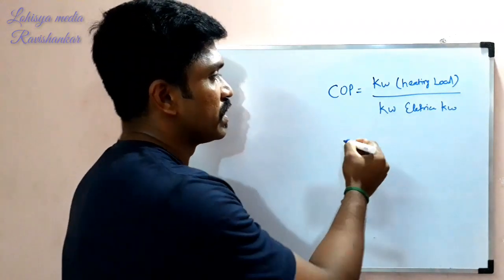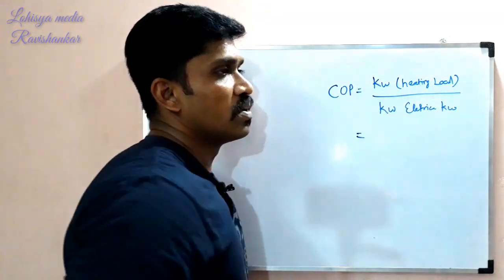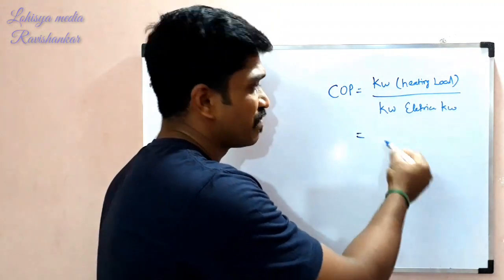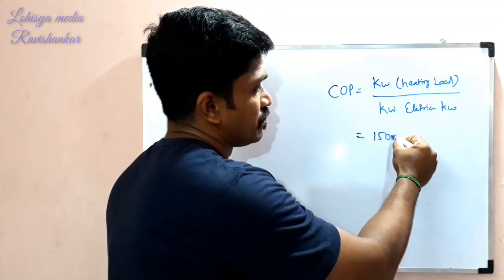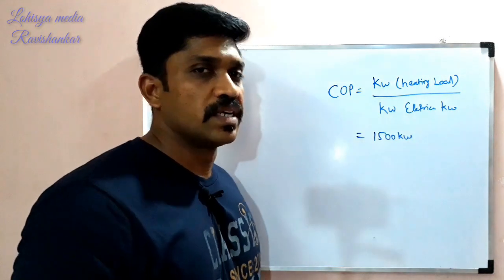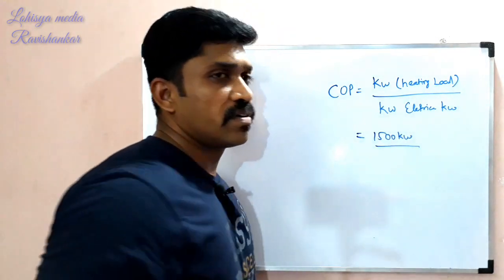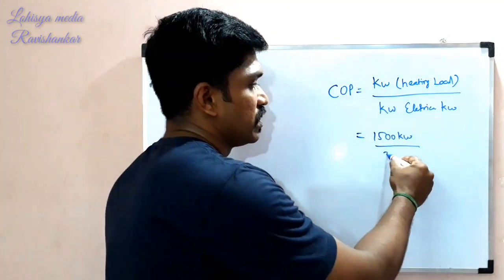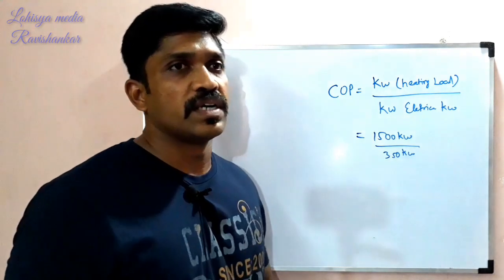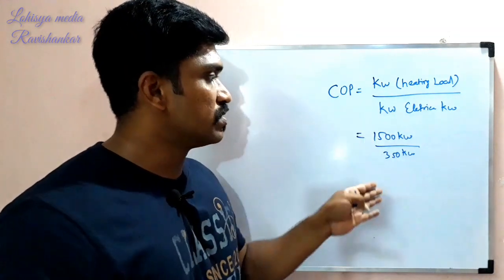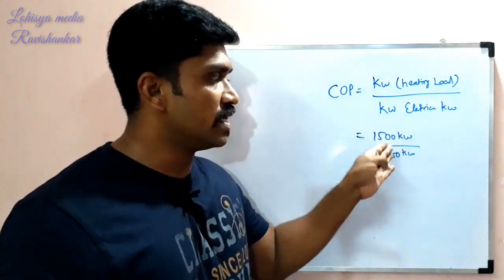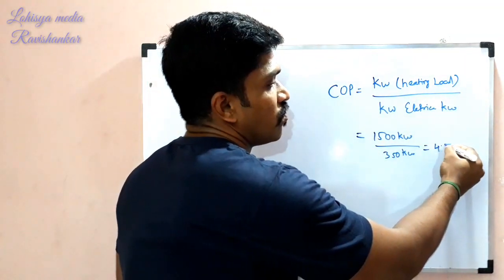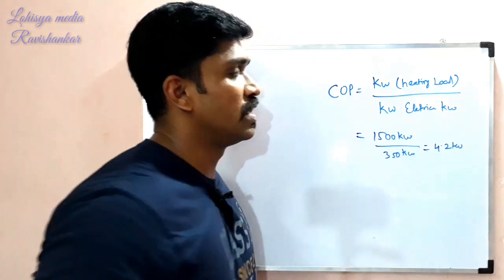Let's say a COP example. The heating load — the chiller capacity — suppose 1500 kilowatt heating load. Now the power input is 350 kilowatt. Now, the COP is 4.2 — kilowatt heating load divided by kilowatt power input.